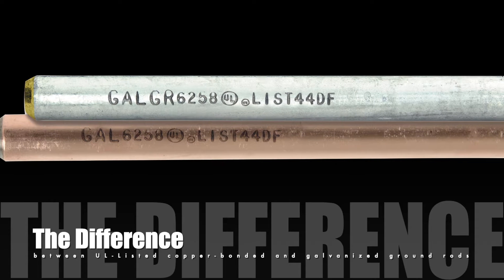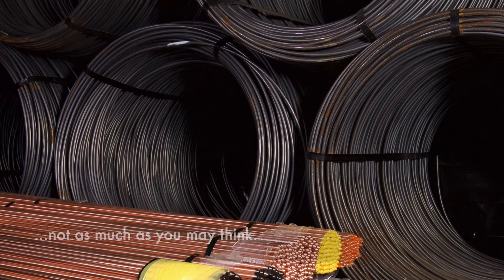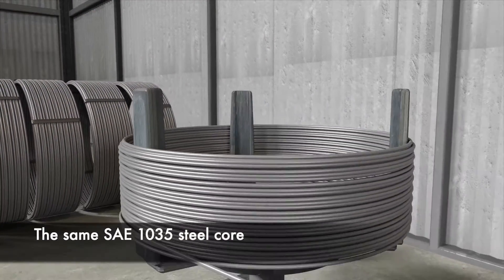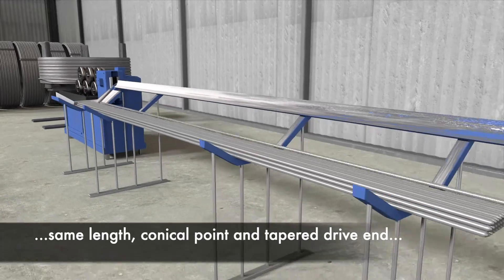What's the difference between Galvan's UL-listed copper-bonded and galvanized ground rods? Not as much as you may think. They're both made from the same cold-drawn SAE 1035 steel core. They are cut to the same lengths — a minimum of 8 feet — and have the same conical point and tapered drive end.